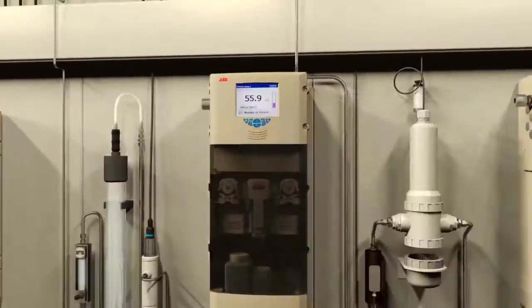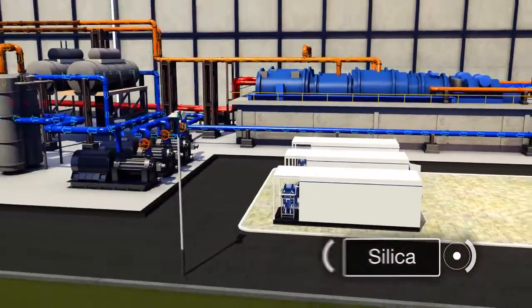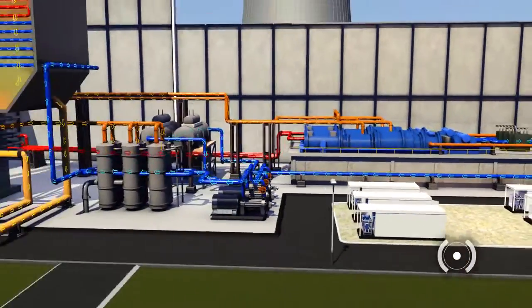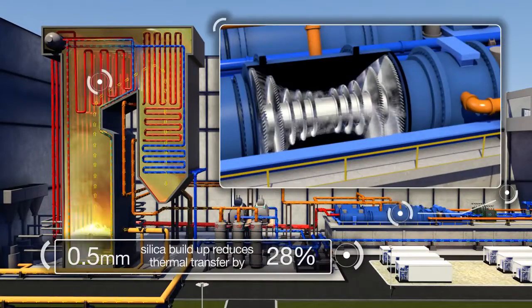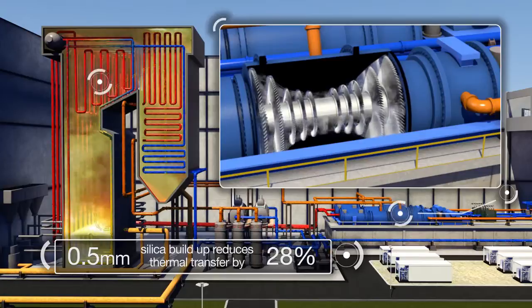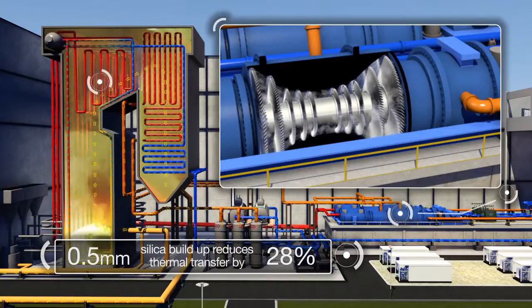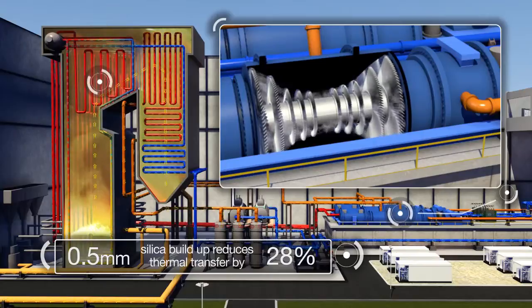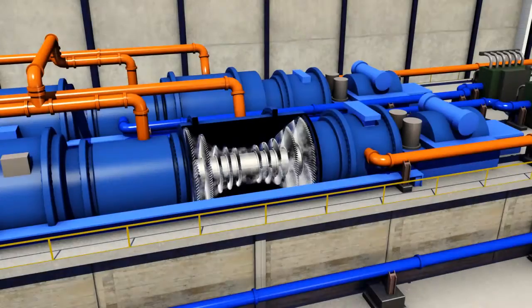Silica forms a dense porcelain-like scale inside the boilers and turbines that cannot be removed even with acid. Its low thermal conductivity means even a 0.5mm build-up of silica can reduce thermal transfer by 28%, leading to reduced efficiency, hot spots and eventual plant failure.